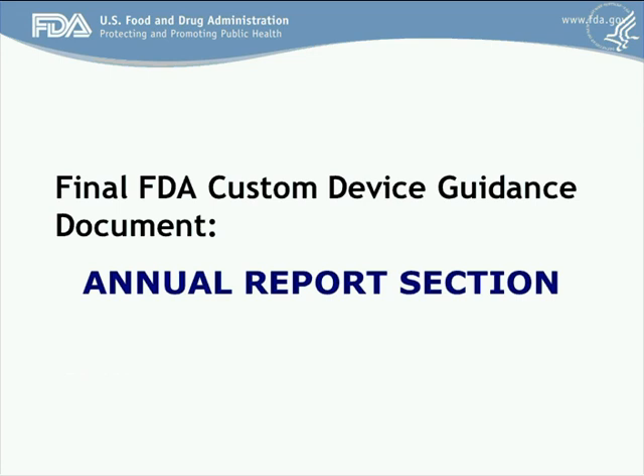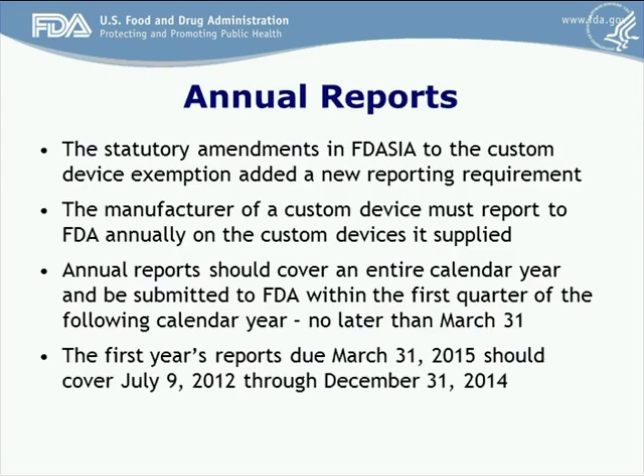Due to statutory amendments to the custom device exemption, manufacturers are now required to submit annual reports. The manufacturer of a custom device must report to FDA annually on the custom devices it has supplied. The annual report should cover an entire calendar year and be submitted to FDA within the first quarter of the following calendar year, no later than March 31st. The first year's report is due on March 31st, 2015, and should cover the period from July 9th, 2012 when FDASIA was enacted, through December 31st, 2014.